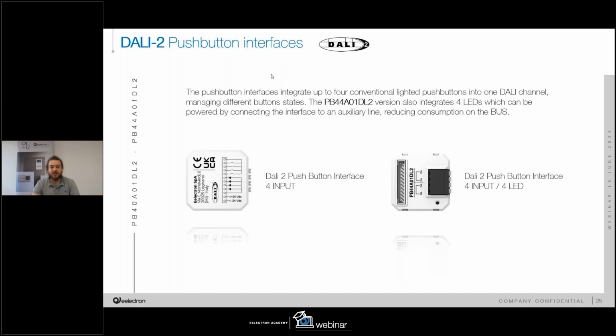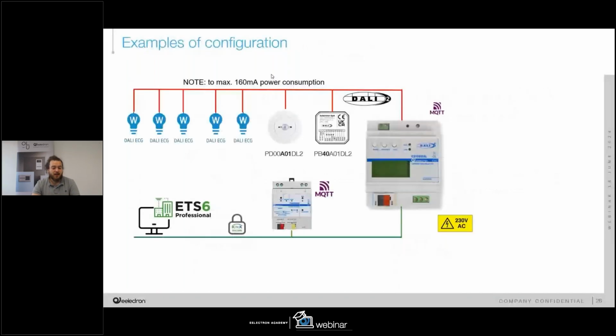In this way, we reduce the consumption of the push button inside the DALI bus. Here we can see some example of configuration where we have a complete solution based in part for the lighting system in DALI, where we have a different DALI ECG, but also one presence detector and one push button interface. This is because with the motion brightness sensor, we can dim up and down the light depending on the actual brightness inside the room, and with the push button interface, we can still enable manual command in order to override the logic of the automatic lighting control system.